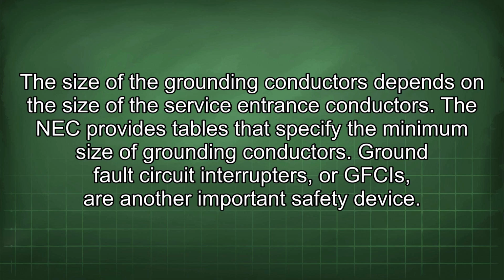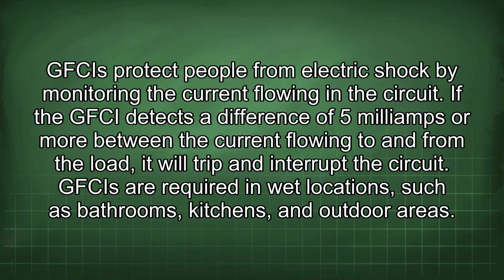Ground fault circuit interrupters, or GFCIs, are another important safety device. GFCIs protect people from electric shock by monitoring the current flowing in the circuit. If the GFCI detects a difference of 5 mA or more between the current flowing to and from the load, it will trip and interrupt the circuit.